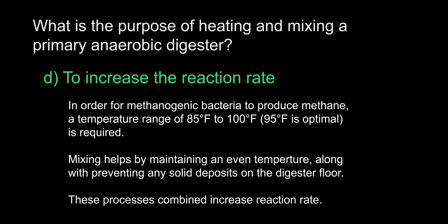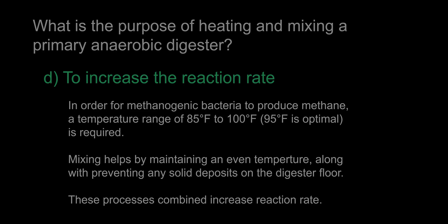The answer is D, to increase the reaction rate. Proper heating and mixing is vital to increasing the biological reaction rate of a primary anaerobic digester. The digester should be heated and kept at 95 degrees Fahrenheit. The distribution of heat is further improved by mixing the contents, along with preventing solids from depositing on the floor, which decreases the total volume within the digester.